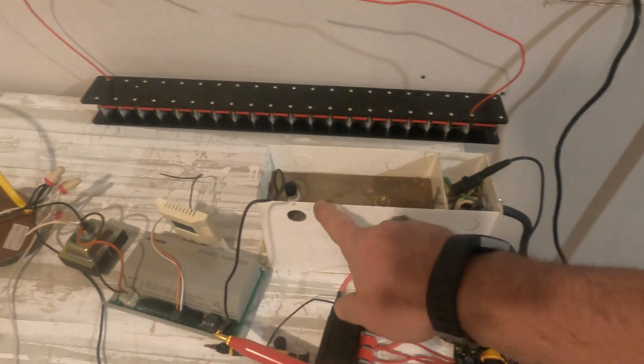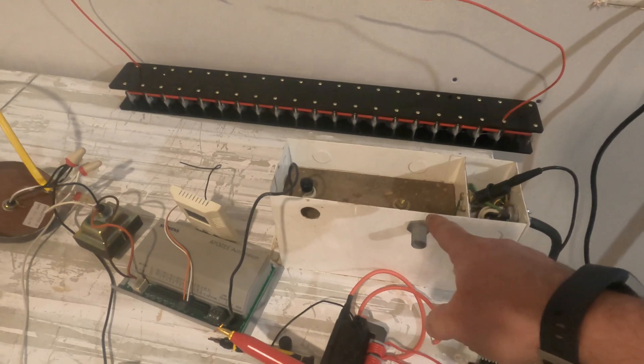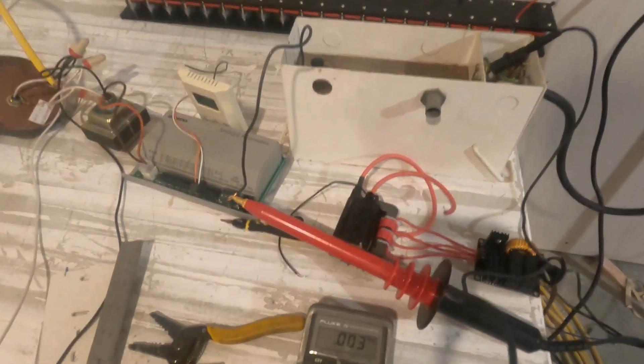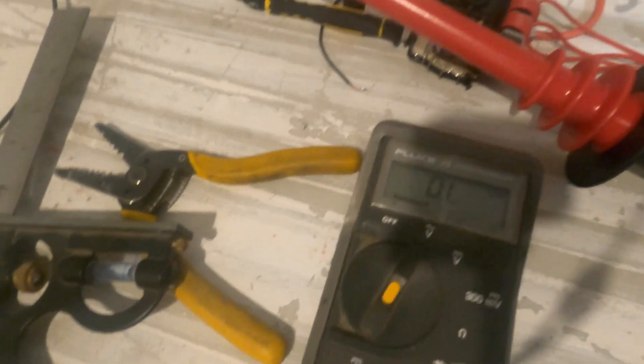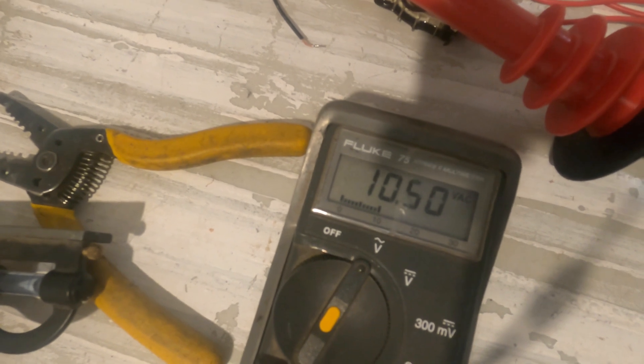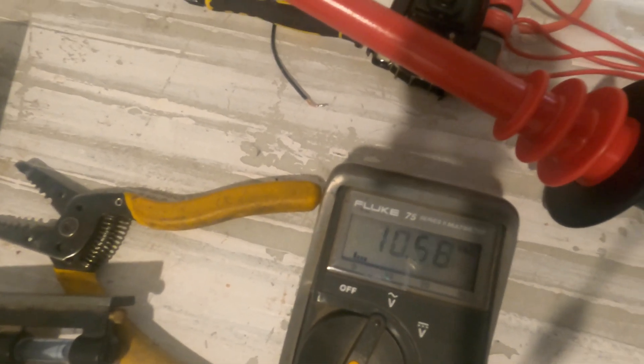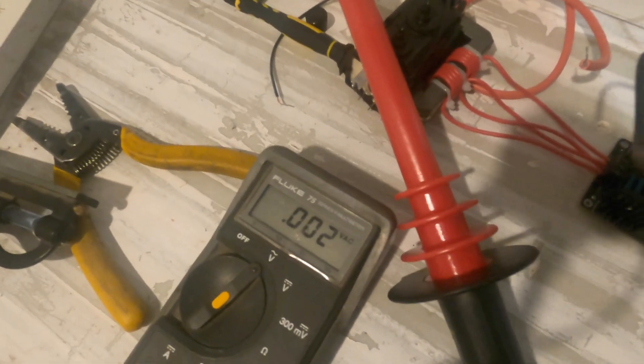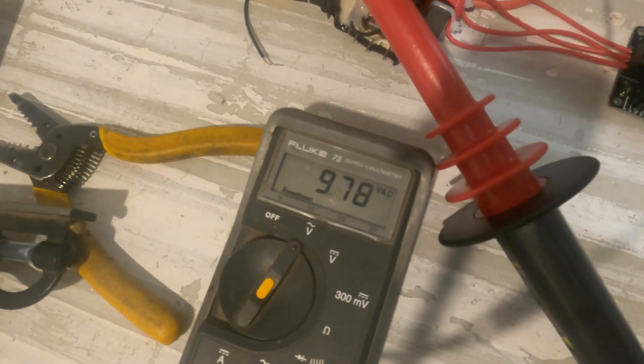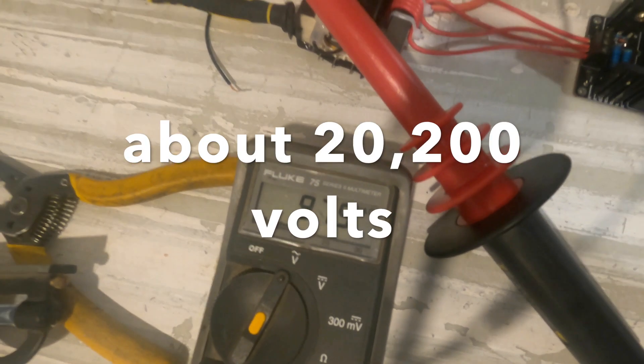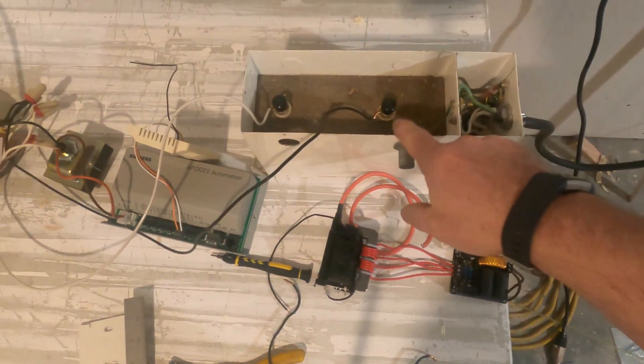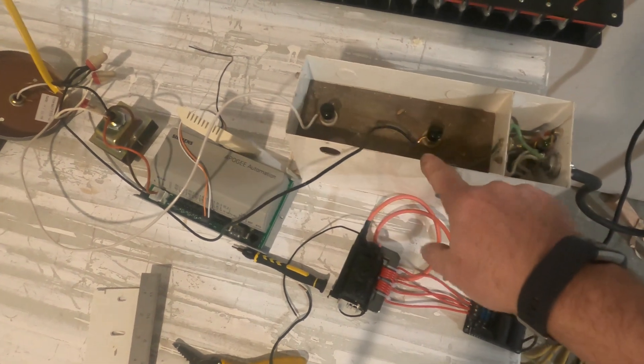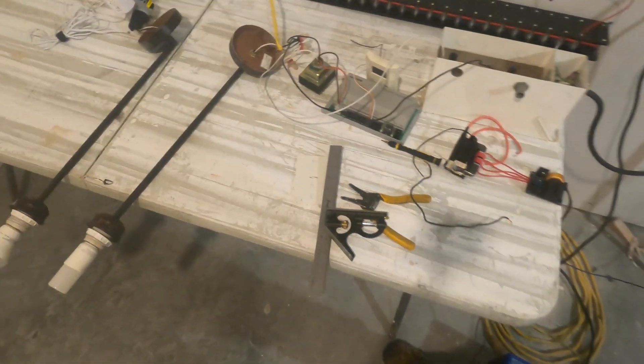So I've got to test each side of this coil to ground. So we'll get half the voltage on this side and half the voltage on that side. And this is our ground probe. All right, power on. Lights go ahead and flicker every time. So we've got 10,500 volts on that one. All right. So we've got the other side hooked up and we'll go ahead and turn on the power. And we have 9,780 on this side. So it's a little bit lower. And just so you can see, I'm hooking up both neutral and hot to each probe. So we're getting the combined voltage of the entire coil.